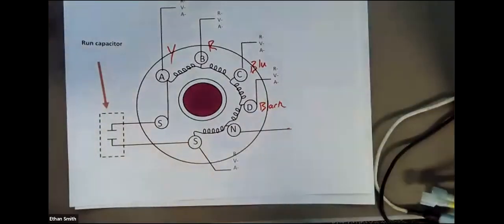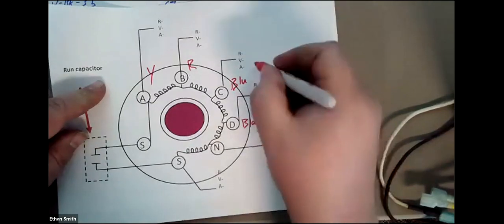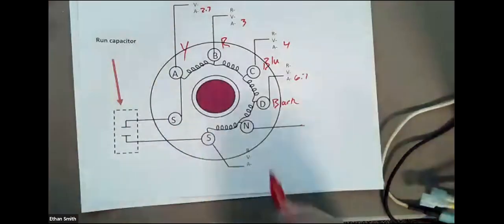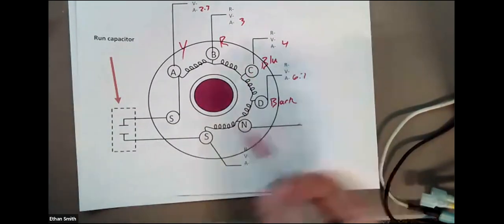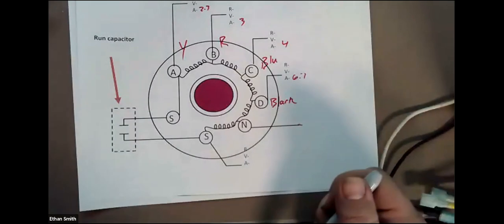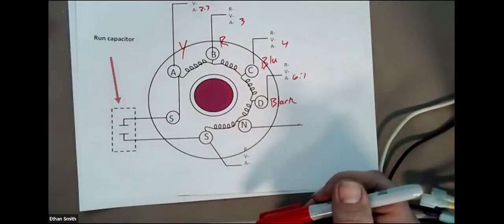So let's go back to my ohm chart. I'll just put rough numbers in here: 6.7, 4, 3, 2.7, approximately, for our ohm rating. What if I were to take my neutral and move it to the blue terminal here? What do you guys think would happen? Nothing good? Okay. Wouldn't it depend on where you put your run wire as well?